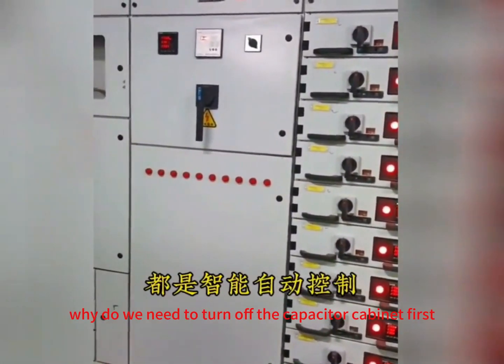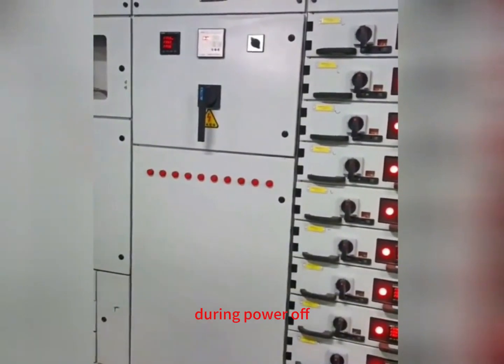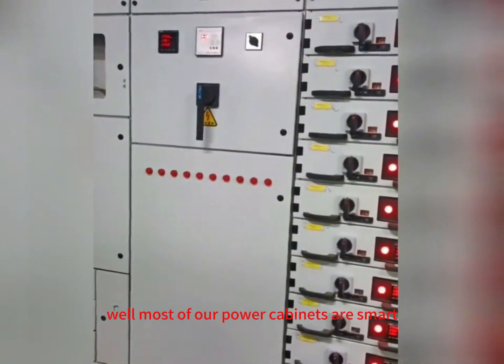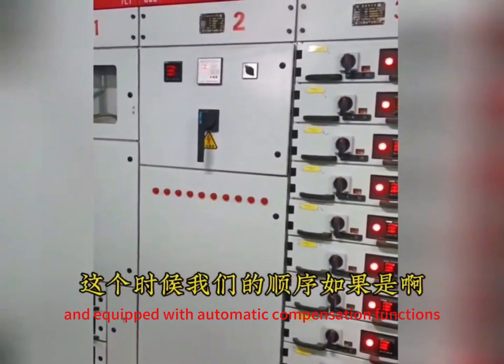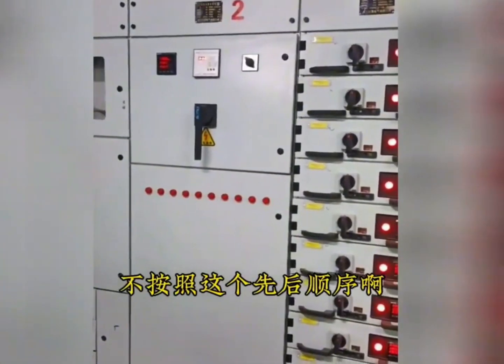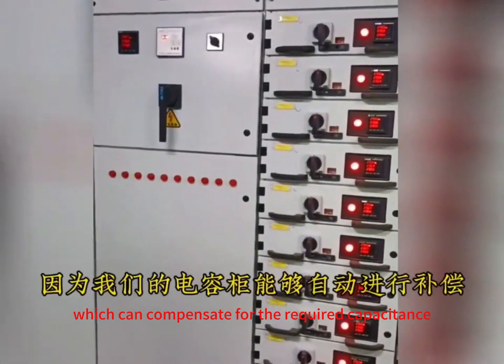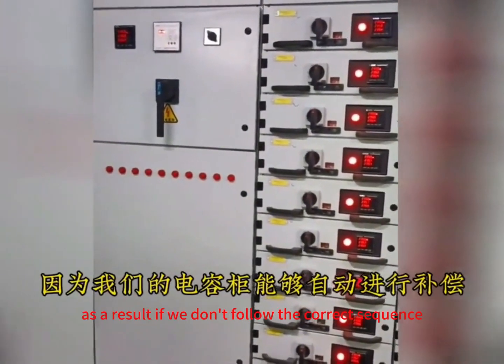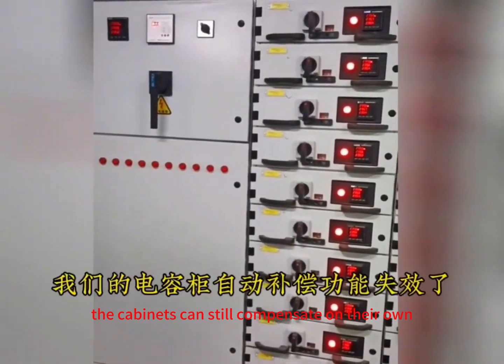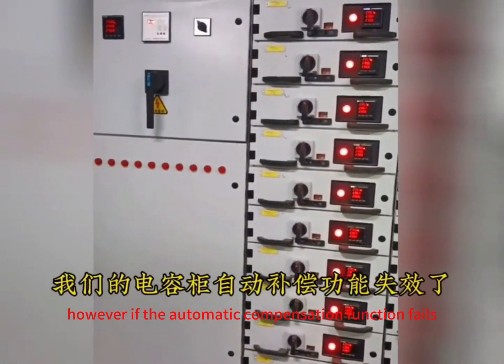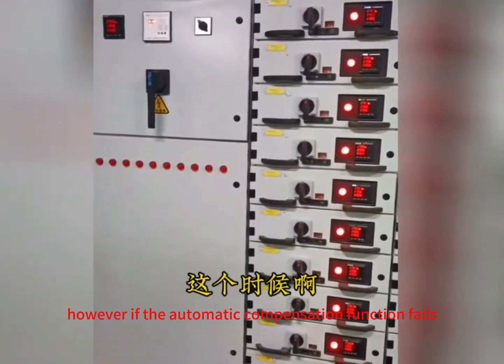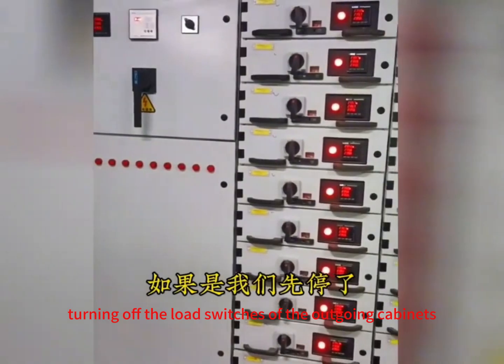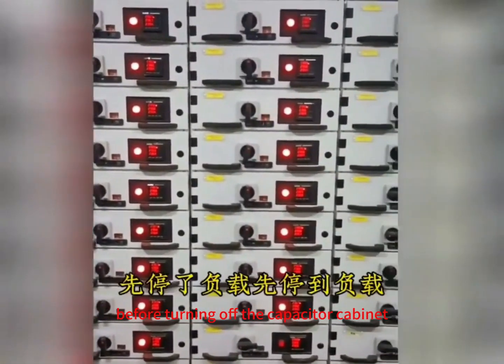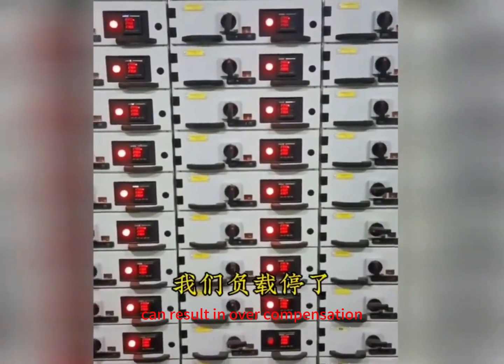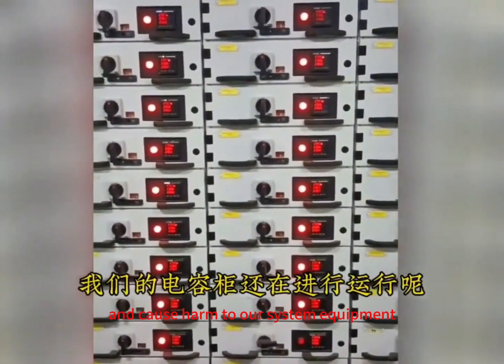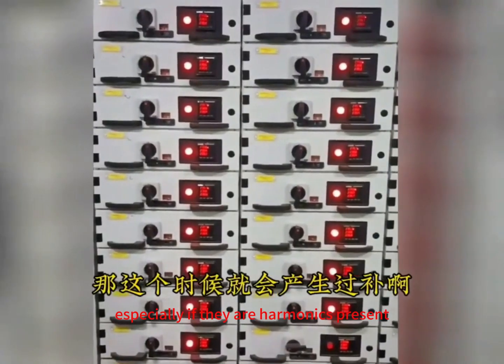Now, why do we need to turn off the capacitor cabinet first during power off? Well, most of our power cabinets are smart and equipped with automatic compensation functions, which can compensate for the required capacitance automatically. As a result, if we don't follow the correct sequence, the cabinets can still compensate on their own. However, if the automatic compensation function fails, turning off the load switches of the outgoing cabinets before turning off the capacitor cabinet can result in overcompensation and cause harm to our system equipment, especially if there are harmonics present.